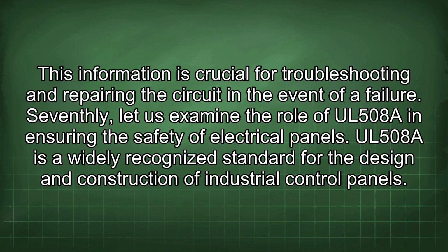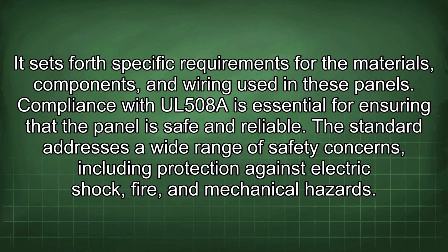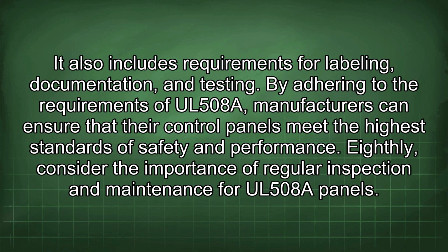UL508A is a widely recognized standard for the design and construction of industrial control panels. It sets forth specific requirements for the materials, components, and wiring used in these panels. Compliance with UL508A is essential for ensuring that the panel is safe and reliable. The standard addresses a wide range of safety concerns, including protection against electric shock, fire, and mechanical hazards. It also includes requirements for labeling, documentation, and testing.